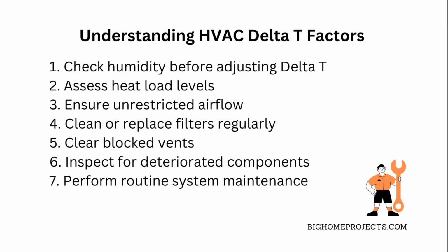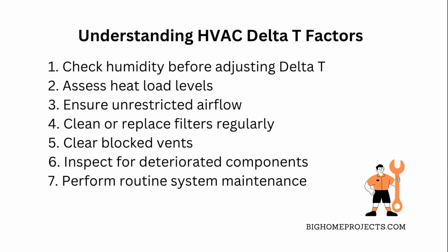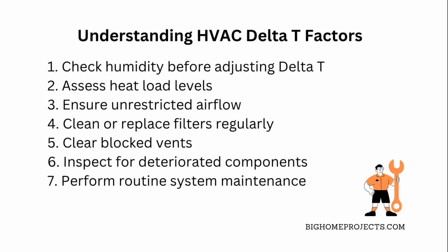Also, eyeball the airflow with your hands or a meter. Clogged filters or blocked vents can mess things up big time, and always look over the whole system's condition, like dirty coils or leaks, since those mess with performance and your Delta T numbers.